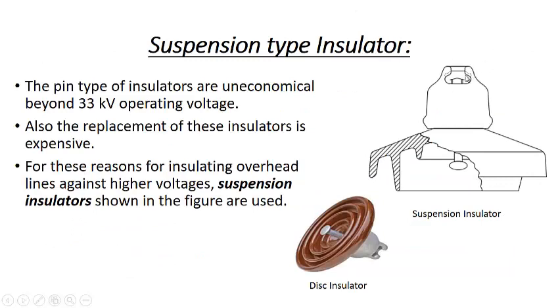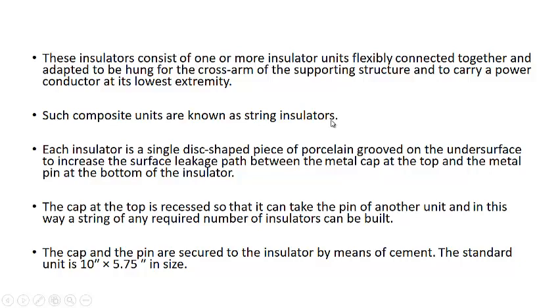You can see we have a cap over here. This is the pin over here. This pin may fit over here into another insulator to make the string of insulators. The cap and the pin are secured to the insulator by means of cement. They are finally bound by means of cement. The standard unit is 10 inch by 5.7. 10 inch is the diameter, 5.7 is the height.